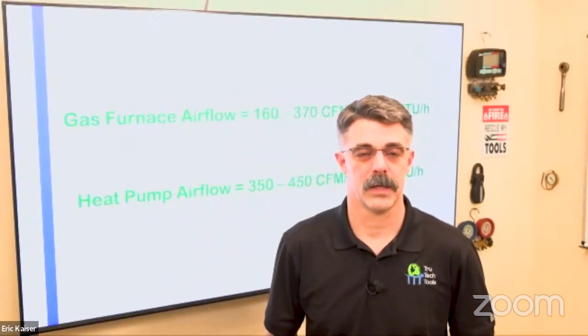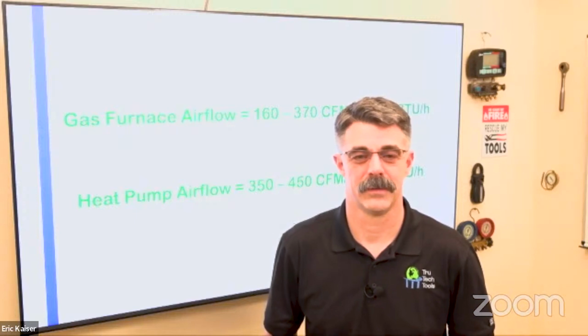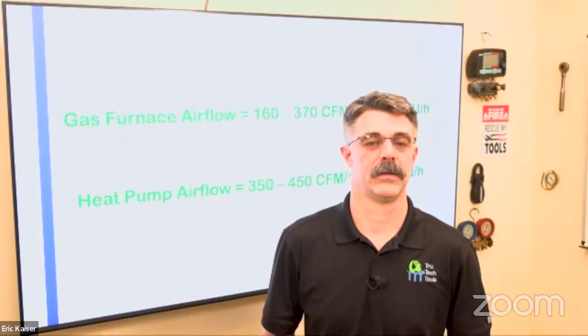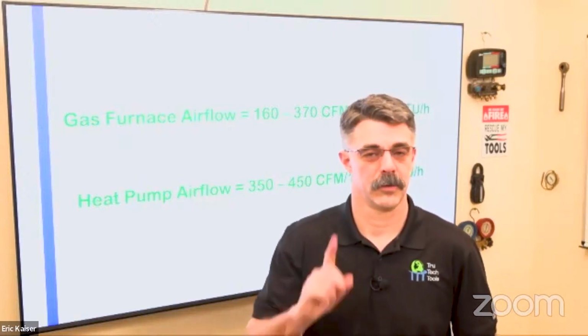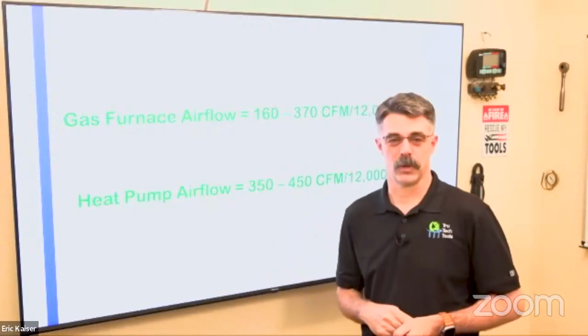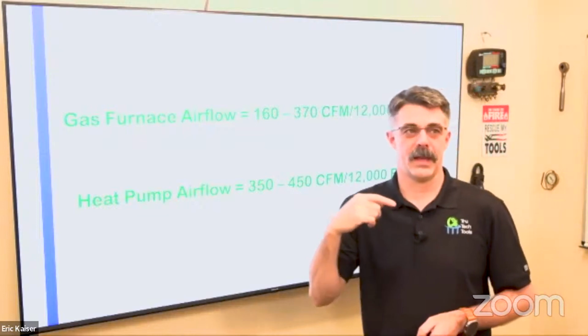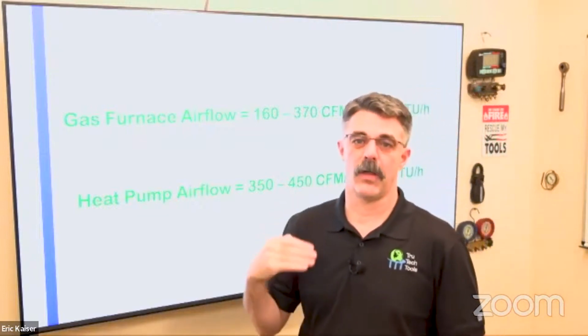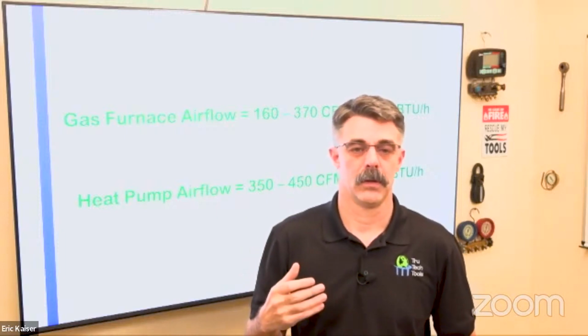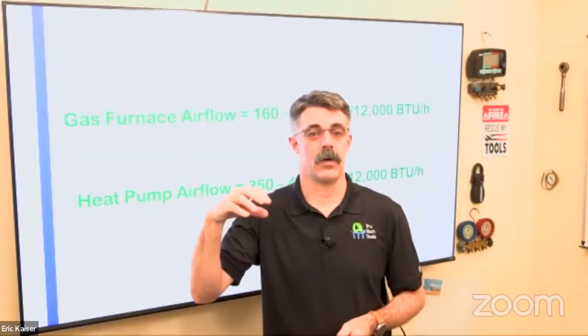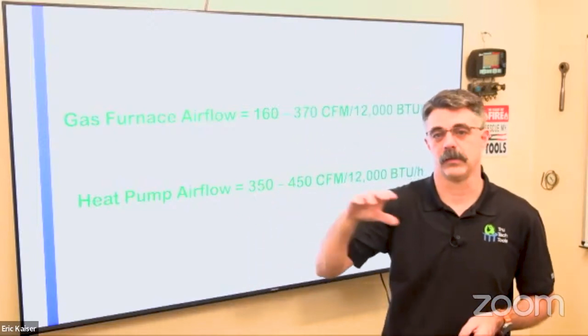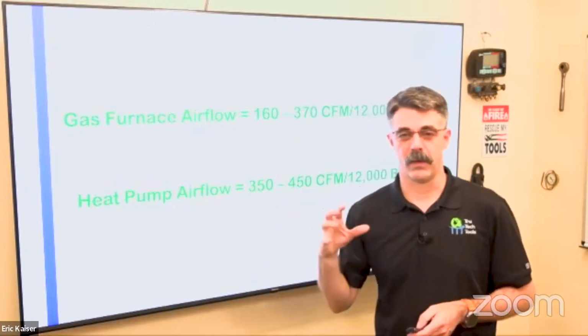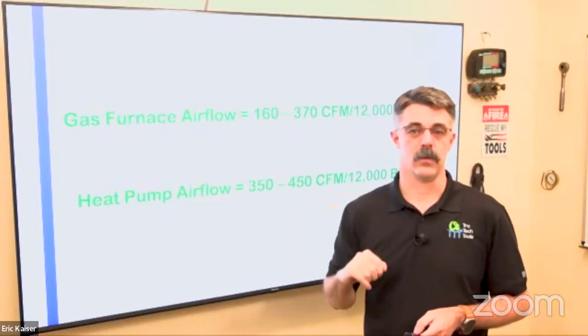Now, we have a question. It's from Keith Keller. Hi, Keith. Sometimes you can adjust the airflow with the air handler. How do you determine the best fan speed for a system? Where does that fit in your process? Great question. We'll get to that in a little bit, and I'll say it's based on the performance data of the equipment. What that means is you've got to get into the performance data, figure out how many BTUs you need and how much airflow that equipment needs to deliver that many BTUs. So that's part of the whole process of looking at that performance data, and that's part of going through Manual S.